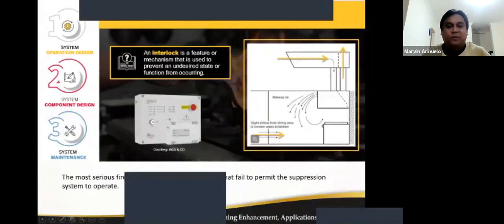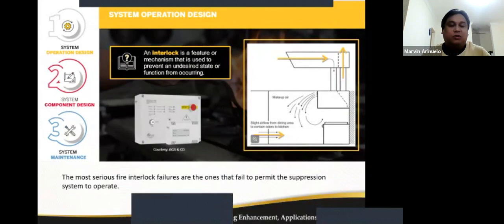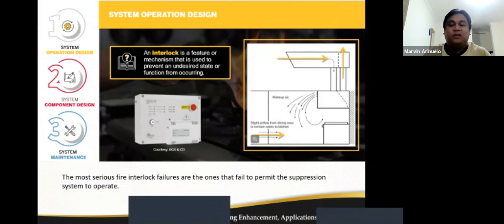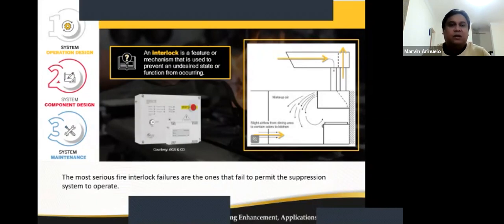and frequent replacement whenever required according to your authority having jurisdiction requirements and NFPA requirements. Again, in system operation design, one of those is the interlocking system. And this is one of the greatest failures, failing to permit the suppression system to operate.